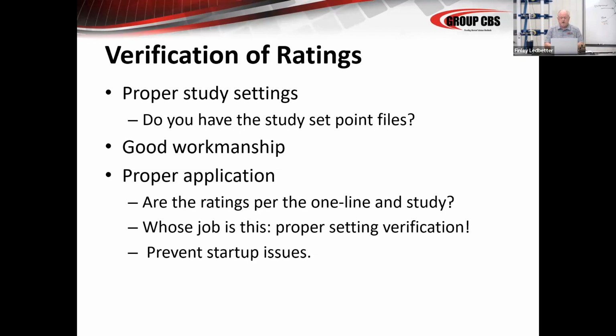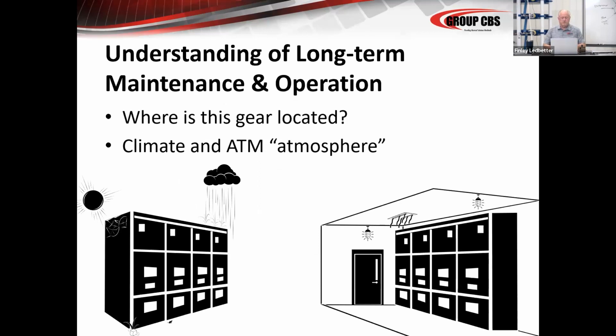Proper applications are the ratings per the one line and the study, whose job was to properly verify it. That'll help you prevent startup issues. It is real important, I want to say this one more time, to understand the long-term maintenance and operation of the equipment. Where's the gear located? What's the climate? What's the atmosphere? Is it indoor gear? Is it outdoor gear? Does it look like it will protect the equipment correctly for a long period of time? I've seen seams. I've seen buildings not assembled correctly where you could look through and see a gap in the edge. That's the sort of thing you need to look for.